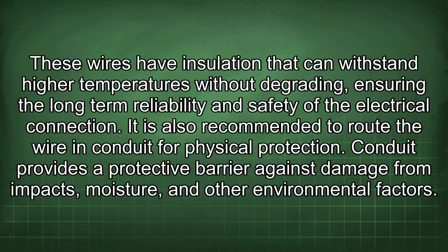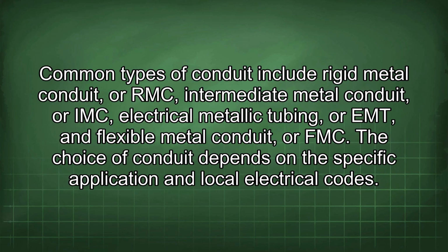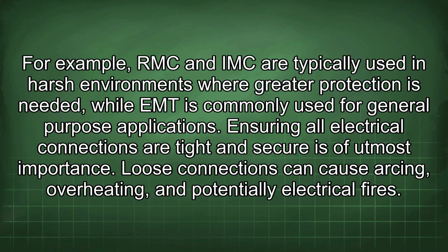It is also recommended to route the wire in conduit for physical protection. Conduit provides a protective barrier against damage from impacts, moisture, and other environmental factors. Common types of conduit include rigid metal conduit, or RMC, intermediate metal conduit, or IMC, electrical metallic tubing, or EMT, and flexible metal conduit, or FMC. The choice of conduit depends on the specific application and local electrical codes. For example, RMC and IMC are typically used in harsh environments where greater protection is needed, while EMT is commonly used for general-purpose applications.